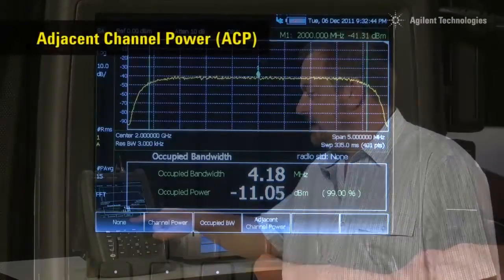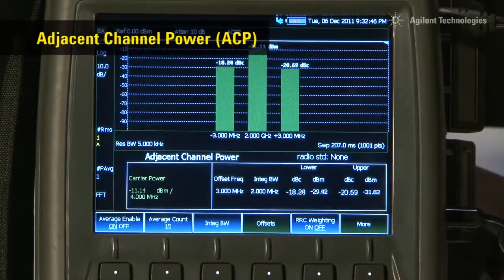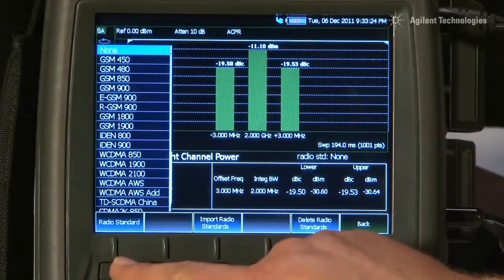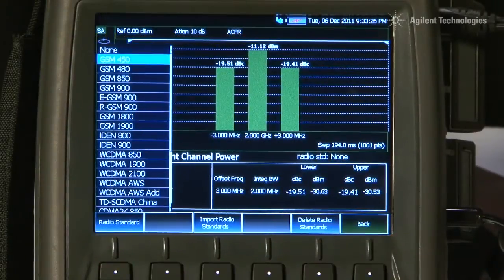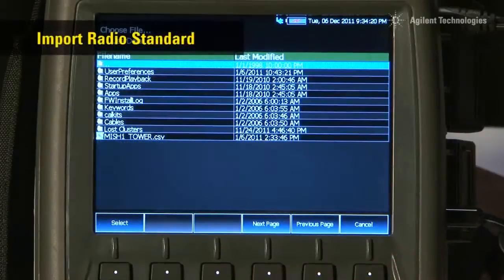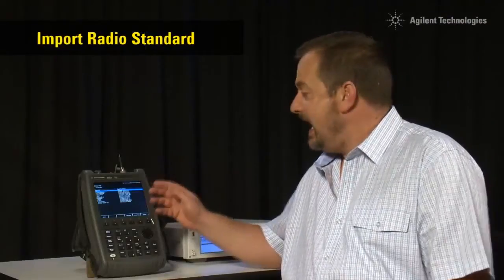We can even measure the adjacent channel power, and if we are working to a radio standard, such as in this case WCDMA, we can recall that standard, and the adjacent channel power measurement will automatically configure itself to measure adjacent channel power properly for that radio standard. You can even import your own radio standard. You just create them on your PC and then load them in on a USB memory stick.